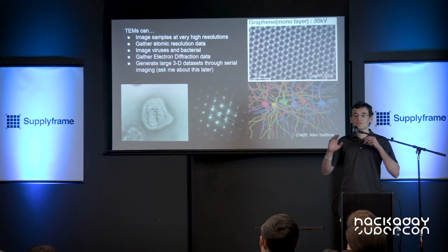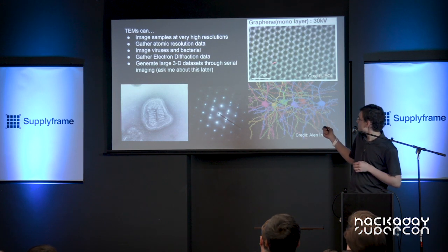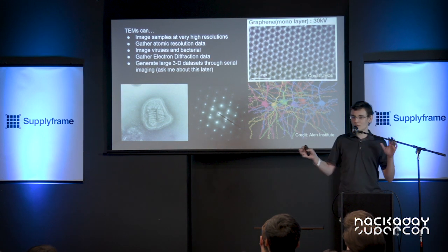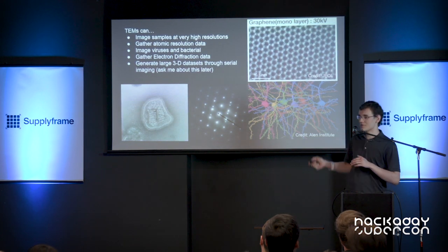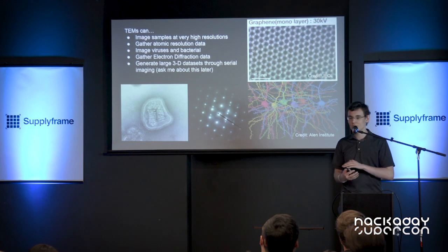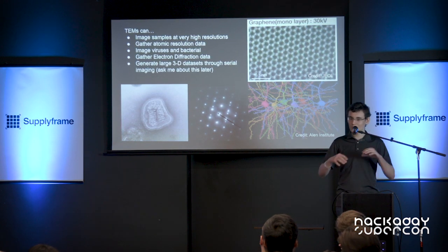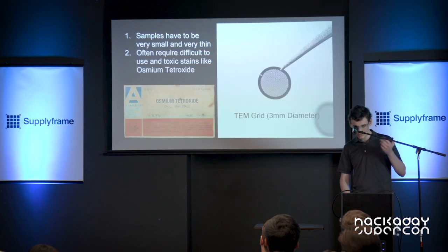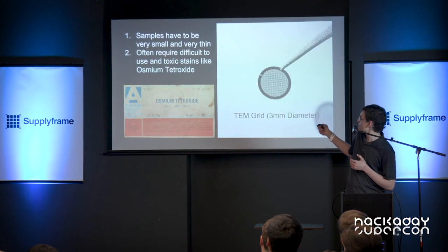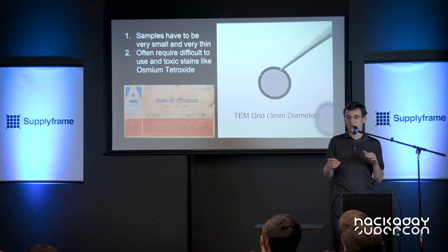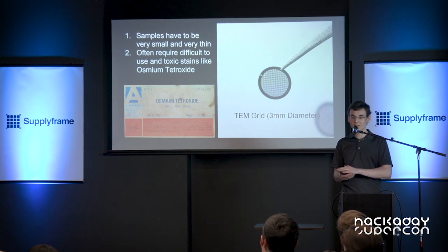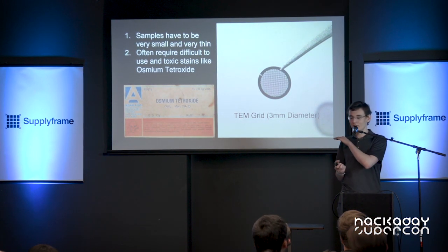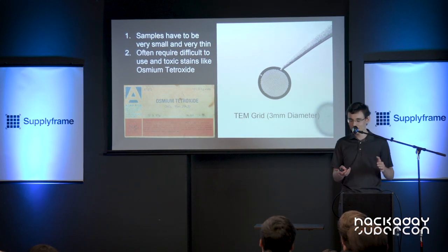However, the data they produce is incredible. We can make atomic resolution images, we can take pictures of viruses, we can extract electron diffraction data, and with some specialized tools we can even reconstruct the interconnections between neurons in a brain at a level where we can see where they touch. If you ever come across one, you're going to be preparing your samples on grids — a three millimeter copper grid. You have to suspend a 70 to 150 nanometer thick sample on top of it, just because it has to be that thin for the electrons to go through. Getting a sample that thin involves diamond knives, or ion beam milling, or all sorts of crazy technologies.